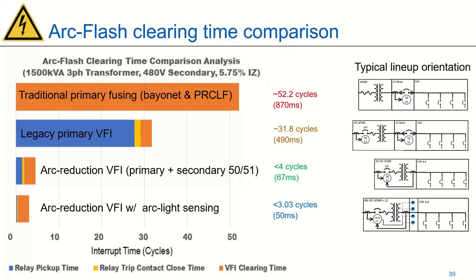The key here is that you've got something that's electronically trippable on the primary, something you can send that trip signal to, and instead of having to wait for that fuse, you have this electronically trippable interrupter that can react much faster. So it's the relay and the CTs on the secondary that are doing the reaction and then sending that signal. But the fact that you have that electronically trippable VFI is what's going to give you that ultimate speed.